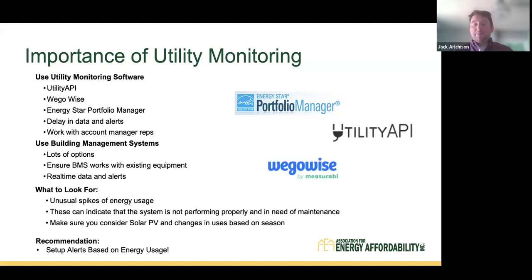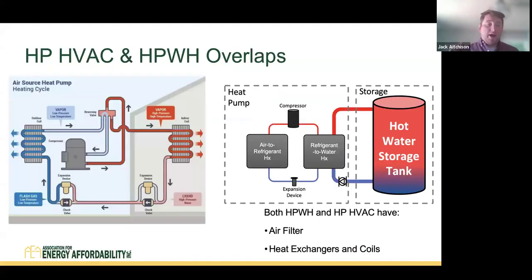I'll run through these quickly: heat pump HVAC and heat pump water heater overlaps. As Scott mentioned, you have this whole refrigerant cycle. Fortunately, if you're electrifying both your water heating and space heating, it's the same technology. It may look very different, but the components inside are very similar, and the maintenance requirements are also very similar. You'll have an air filter to swap out, and heat exchangers and coils you may need to clean. So heat pump water heaters and heat pump HVAC systems have very similar maintenance requirements.